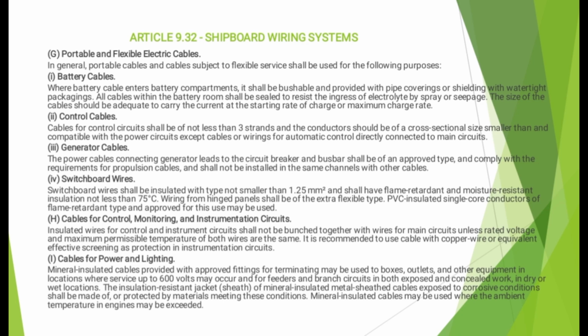Wiring from hinge panel should be extra flexible and PVC insulated. Instrumentation circuits: insulated wires for control and instrument circuits should not be bundled with wires for main circuit unless voltage and temperature ratings are the same at the same time. Cables for power and lighting. Mineral insulated cables with approved fittings can be used up to 600 volts in exposed, concealed, dry, or wet locations.